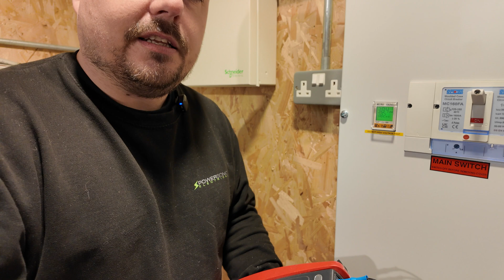We've got about 245 volts between line and earth, and line and neutral. If I hit test now on the half-time test, it shouldn't trip, but you can see we did get that jump, a little spike. I'll run it again and pay attention so I can read it. It's jumped up to 15 milliamps, showing this is doing a good job on the half-time test.